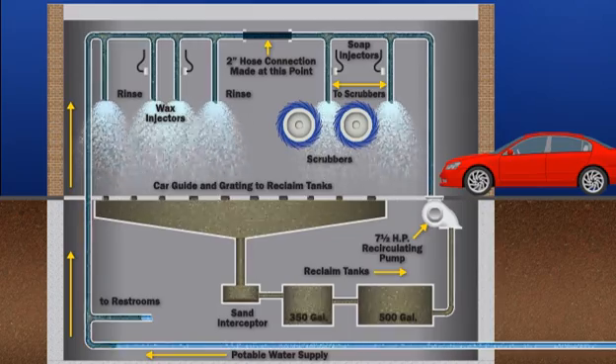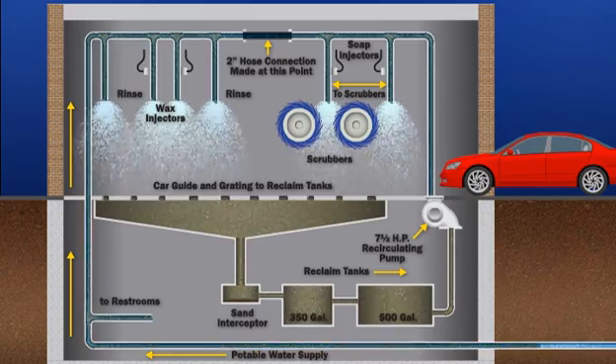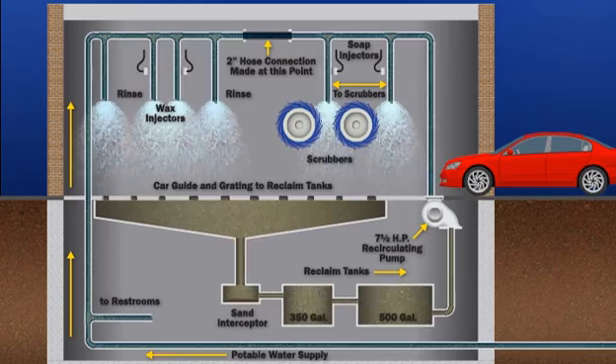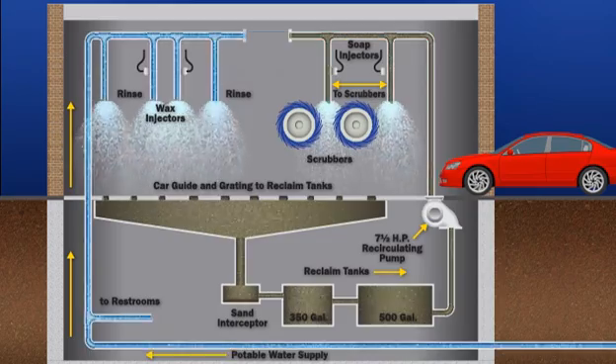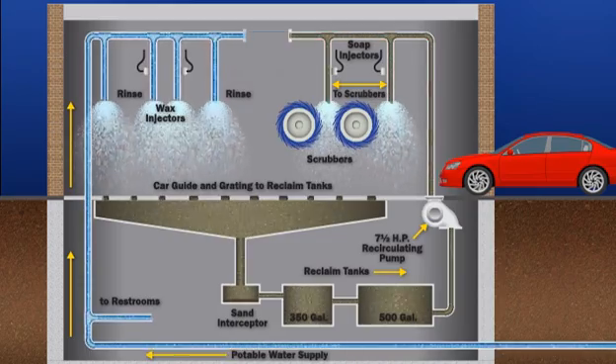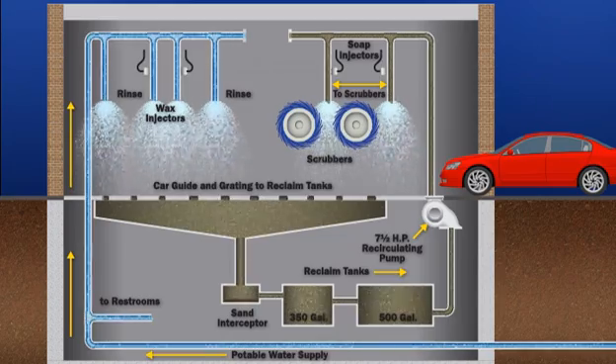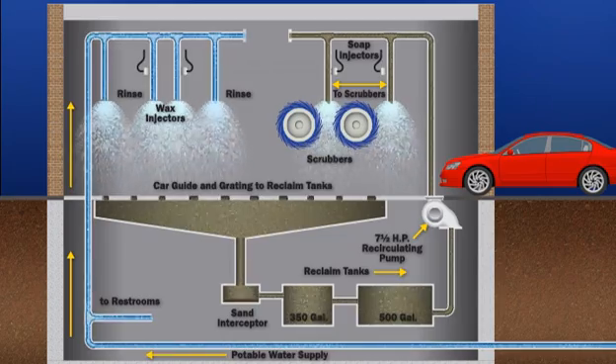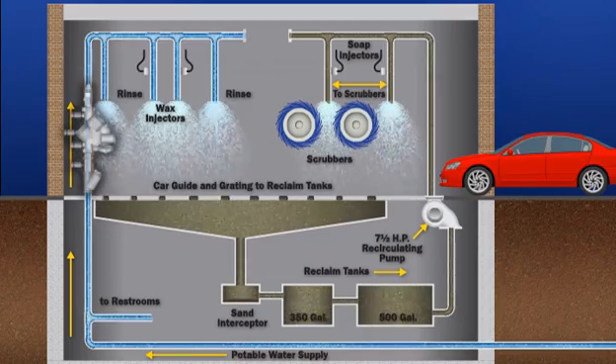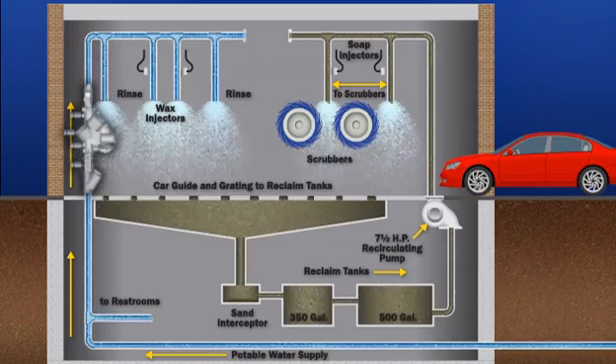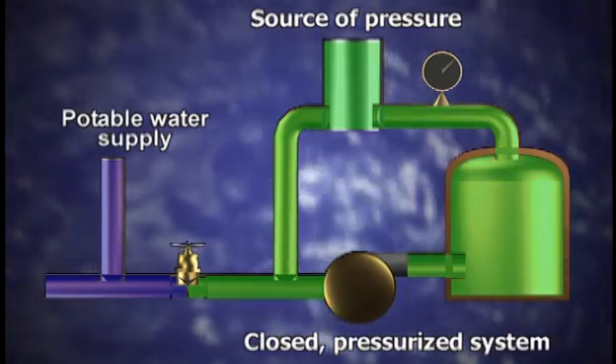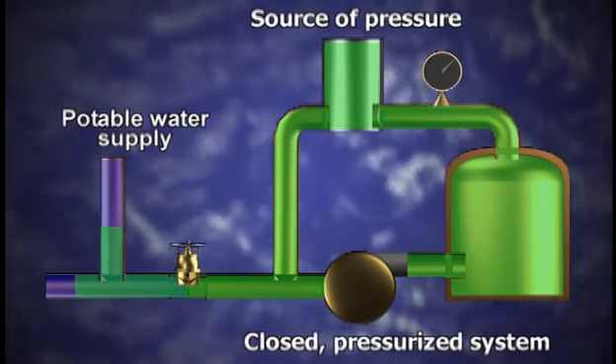The pump forced the contents of the two reclaimed tanks — 850 gallons — into the drinking water main. It didn't take long before a car wash employee noticed brown soapy water in the restroom. The cross-connected two-inch hose was immediately removed, but not before contaminating an eight-block area. The water mains were flushed and chlorinated by the water department, and a reduced-pressure principle backflow prevention device was ordered installed on the water service pipe to provide premise isolation. As you can see, back pressure occurs when the pressure of the connected system exceeds the pressure of the drinking water system, and a higher pressure could force the water to reverse its normal flow, allowing contamination in the drinking water system.